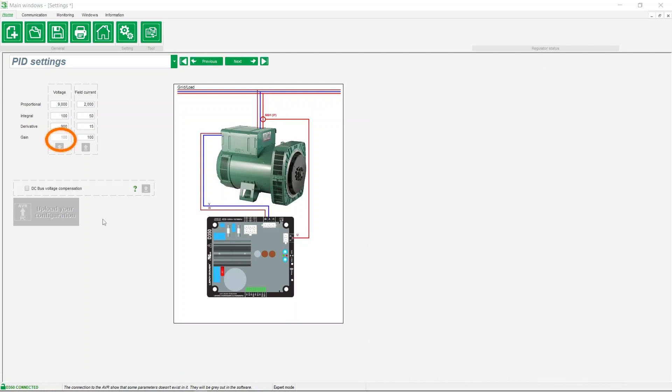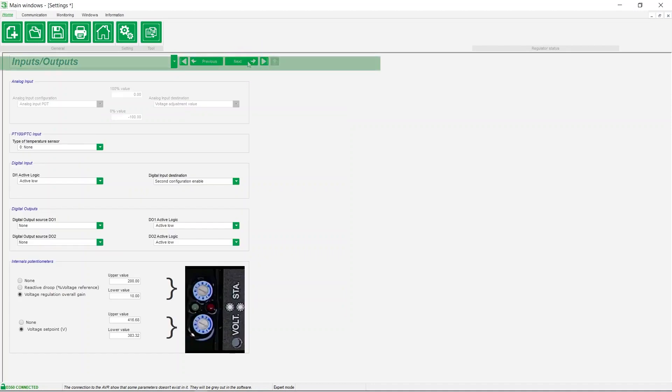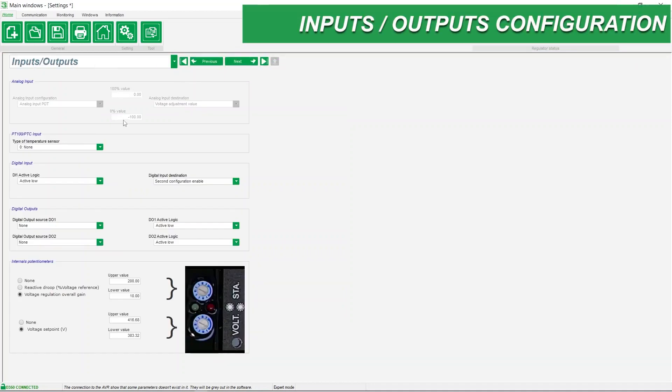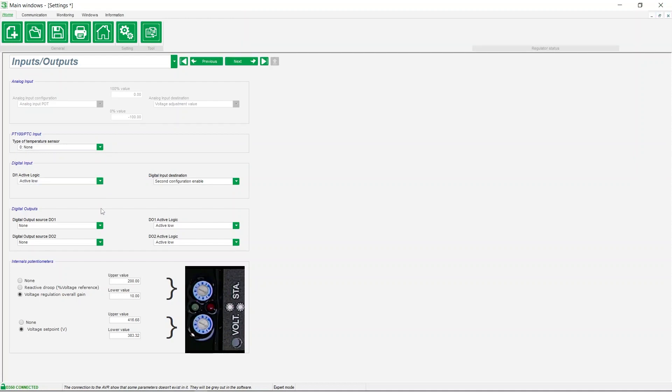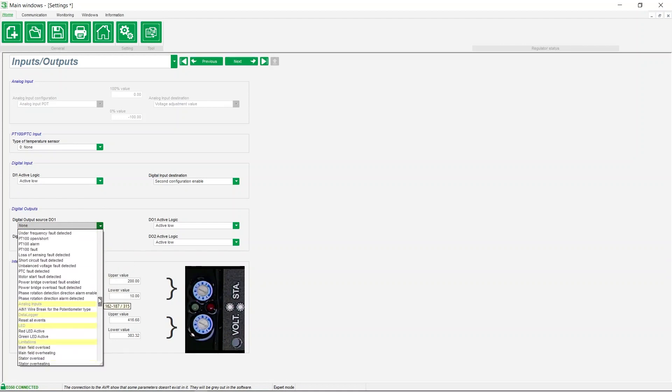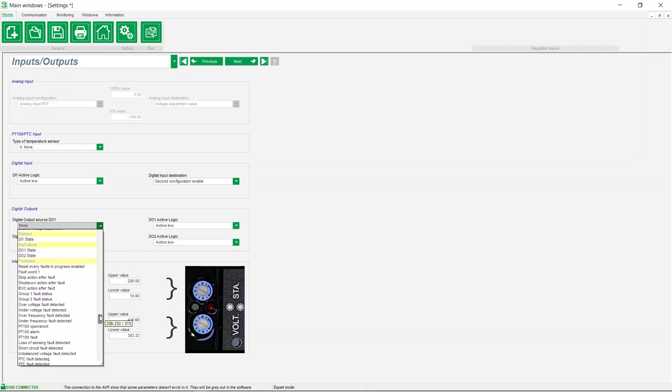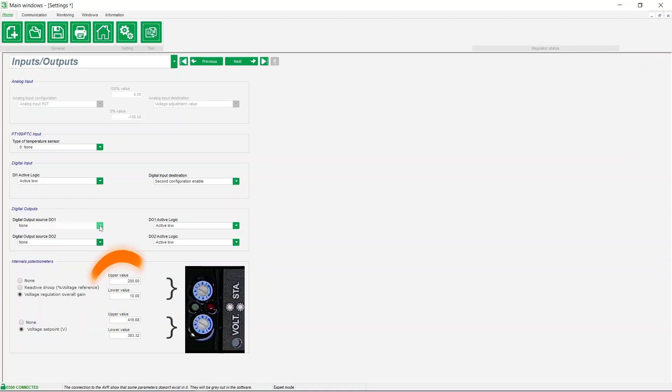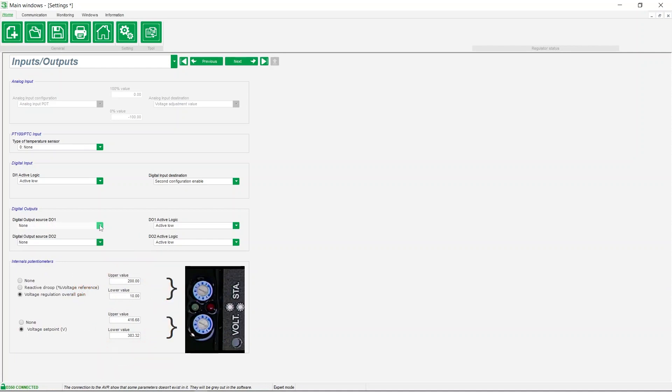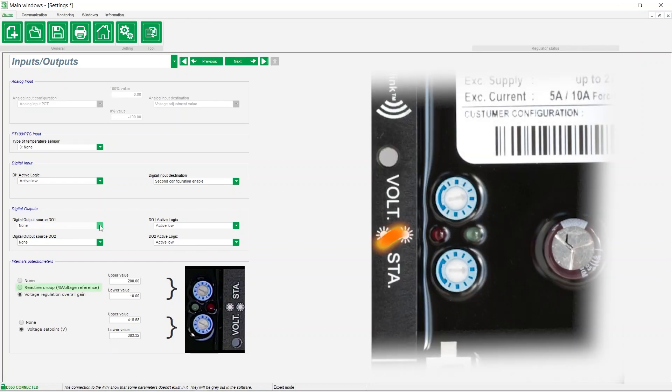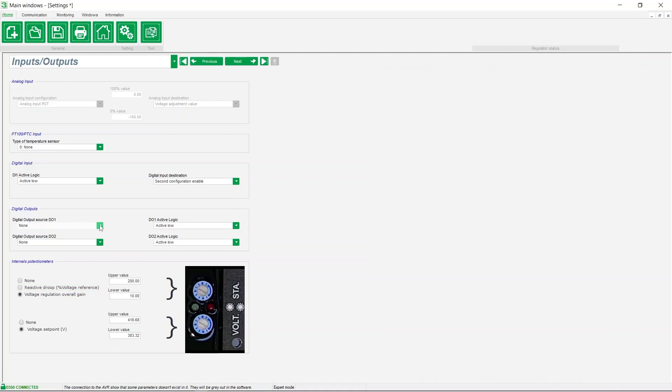Configuration of inputs and outputs: this menu allows you to select an analog input, one digital input, and two digital outputs DO1 and DO2 that can be assigned to events. Here you can easily adjust the upper and lower values of the internal voltage set point and gain potentiometers. You can decide to assign the potentiometer STA to the reactive droop setting instead of the PID gain. This is possible if you have configured a CT in the wiring section.